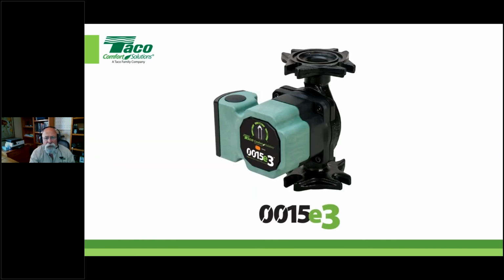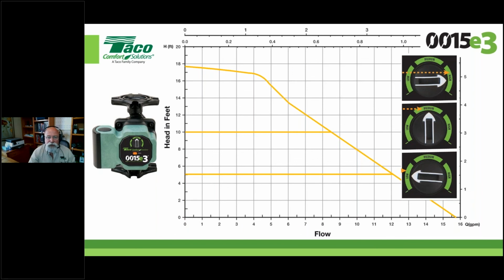Okay. Let's say you've got a 0015 E3. It happens to be on the truck. It's midnight, and I can't turn this pump down to what it should be. Then what is the appropriate mode to use? Well, let's take a look at it, right? You can see here that we've got low is a setting of 5 foot of head under a constant pressure type operating mode. Now, I gave you a caveat when we started here that this is not really the right mode to use, but it works fine as long as you're not anticipating this pump speeding up or slowing down, because it's going to find the resistance of the near boiler piping and the boiler's heat exchanger, and it's going to find its happy spot, and that's where it's going to stay every time it turns on, give or take a little fluid differences in viscosity, right?